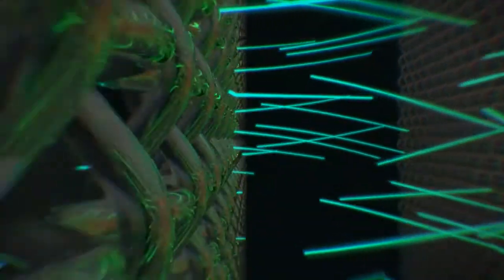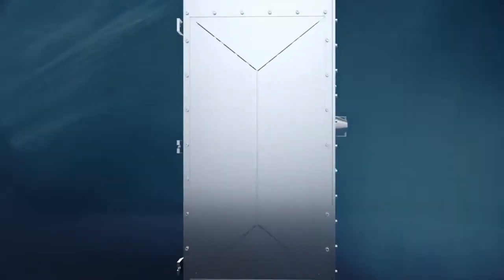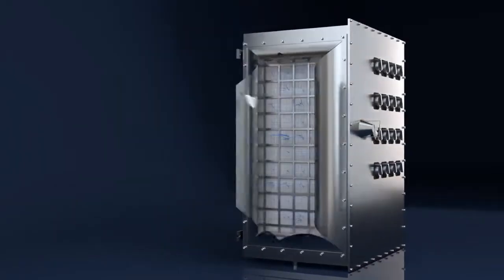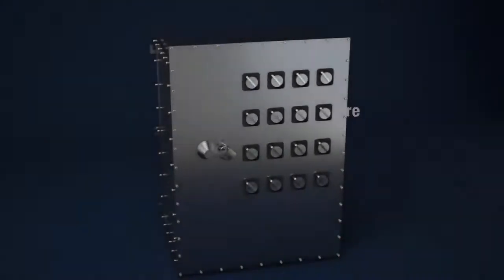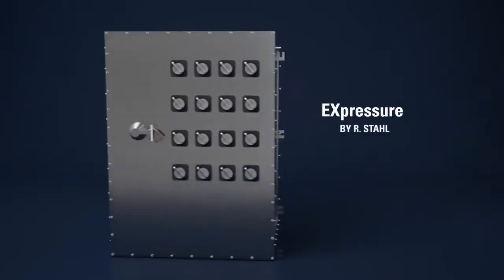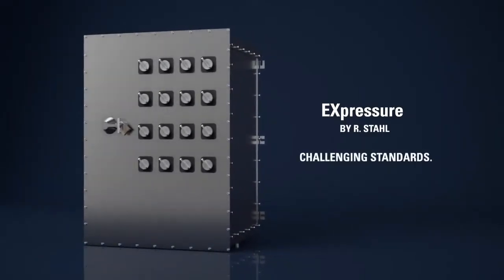When an ignition occurs, its heat and pressure are passed through a complex mesh structure that allows them to bleed off energy. This makes ExPressure 50% lighter than other flame-proof boxes, while offering the same reliable safety. Simply by turning the energy of an explosion into a harmless gust of warm air. ExPressure by R.Stahl, challenging standards.